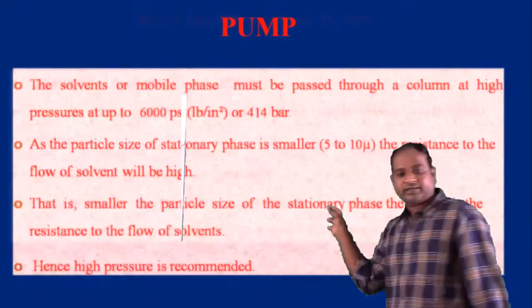Next, coming to the requirements for pumps. Generation of pressure of about 6000 psi is the main requirement for the pump. Pulse free output, that is, the solvent system will flow continuously. It should not break. That is nothing but pulse free output, and all materials in the pump should be chemically resistant to solvent. That is, the pump should be chemically resistant to any type of solvent you are going to use.